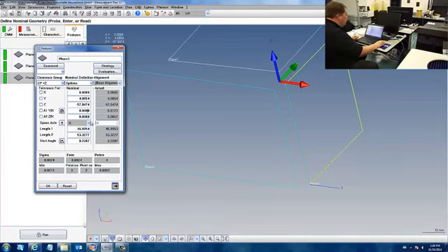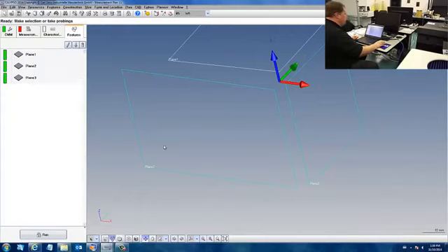What's the benefit of changing these values, though? Well, the first key item for us is that Calypso now can target exactly the right place. When it's driving the probe to these faces, it now has the exact perfect vector to approach the face on.